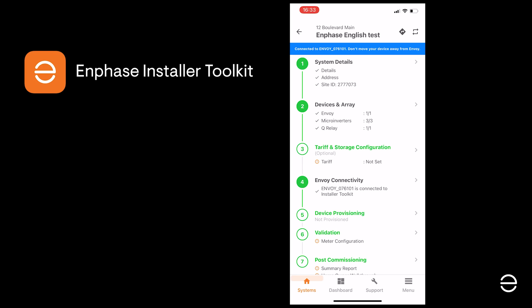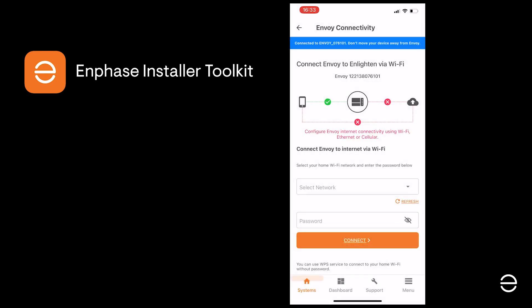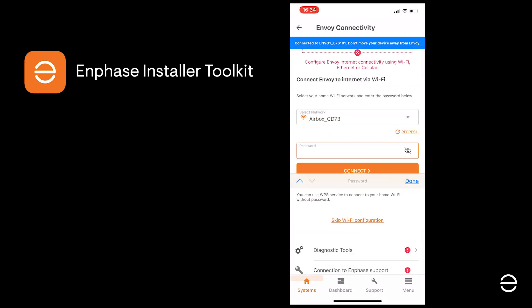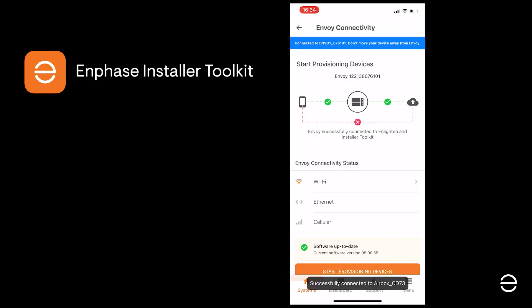Click on Step 5 to start provisioning your devices. To do this, we will need to connect the ITK and the Envoy to Enlighten through the local network. As you can see here, for the moment we're only connected to the Envoy with no internet access. So now you need to select your local network from the drop-down list, enter the correct password and wait for the connection to be established. We can now see that the Envoy is connected to both the ITK and Enlighten through the internet.